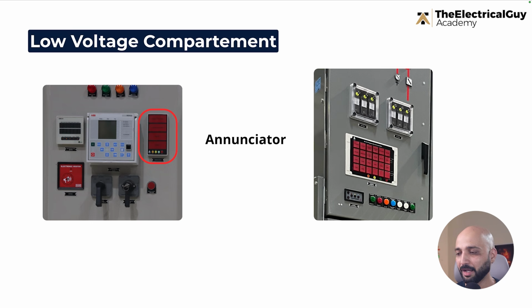Both are giving indications, right? The thing is, you can consider it like this. Indication lamps are used to indicate the status: breaker on, off, close, trip, spring is charged or not charged. Those are the status of things, and that is provided by simple indication lamps.